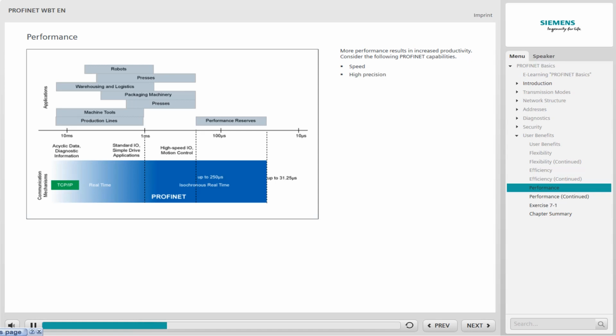Communication via PROFINET is deterministic, which is essential to high product quality. A high degree of accuracy and control quality at a high application speed lead to a significant increase in product quality. PROFINET with IRT allows precise deterministic application behavior, completely independent of the remaining communication load. The implementation of safety applications and standard communication are also possible with short cycle times without restriction.